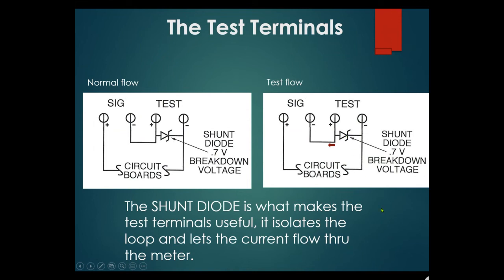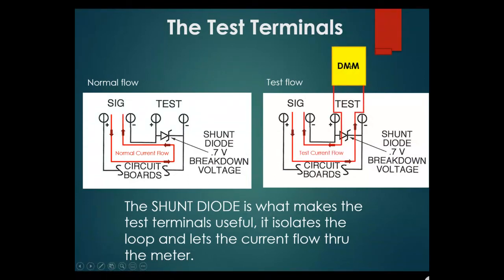Normal current flow goes directly through the transmitter path. When a digital multimeter is connected to the test leads, current flows through the meter instead. You can measure the 4 to 20mA signal or connect a communicator right there. The loop was never broken — you're just bypassing the shunt diode. The digital multimeter picks up the current through what's called the shunt diode.